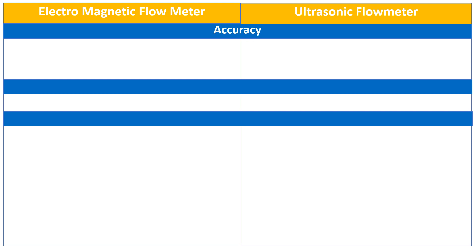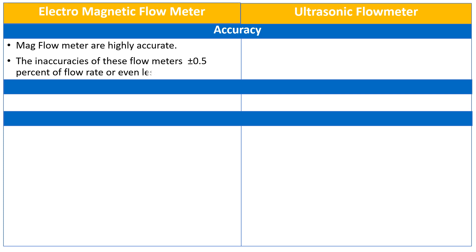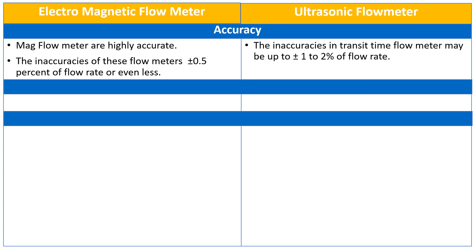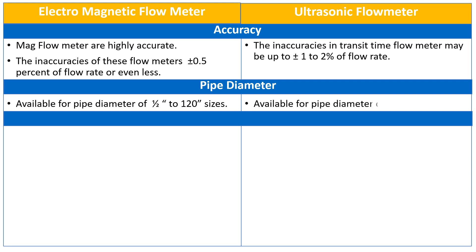The magnetic flow meters are very accurate; the inaccuracies of these flow meters are plus or minus 0.5% of flow rate or even less. The inaccuracies in transit time flow meters may be up to plus or minus 1 to 2% of flow rate. Regarding available sizes, the electromagnetic flow meters are available for pipe diameters of ½ inch to 120 inch, while the ultrasonic flow meters are available in larger pipe sizes.